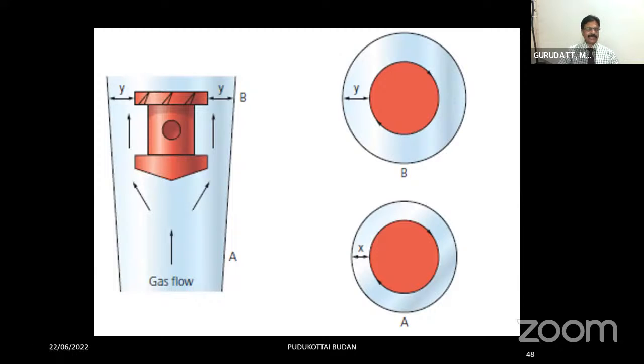So what is the principle behind this bobbin floating at a particular level? Again, there are two forces acting when you open the gases. One force is gravity, because of the weight of the bobbin acting from above, it is trying to push the bobbin down. And the flow of gases will also produce a force which is trying to lift the bobbin higher. When the equilibrium occurs, the bobbin will start floating at a particular level. The upper margin of the bobbin is the one which will give us the indication of what the flow is, because the scale is on the outer aspect of the flow meter. You can just know how much flow. It is not from the middle of the bobbin or from the bottom of the bobbin. It is from the top margin.